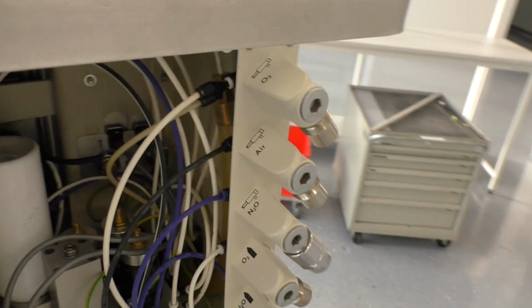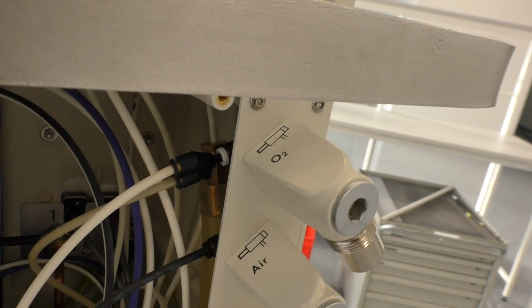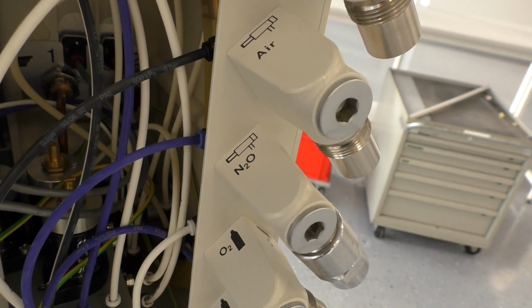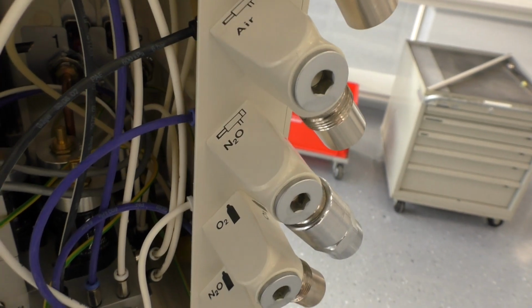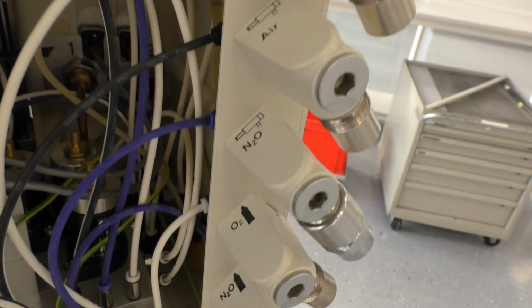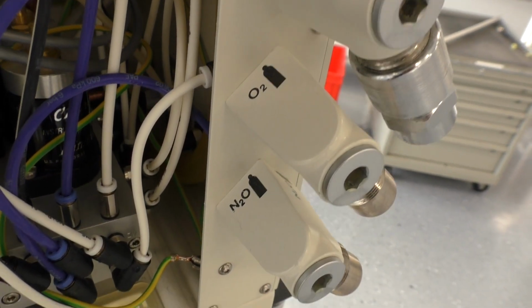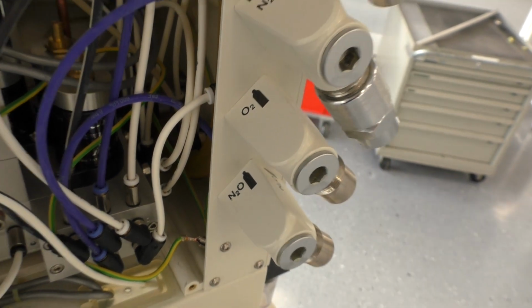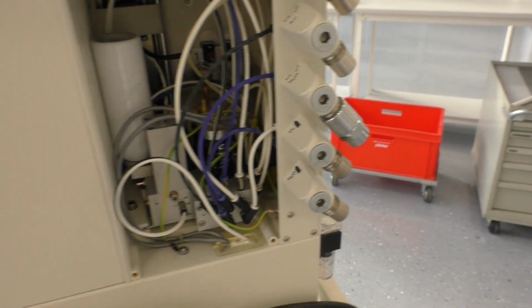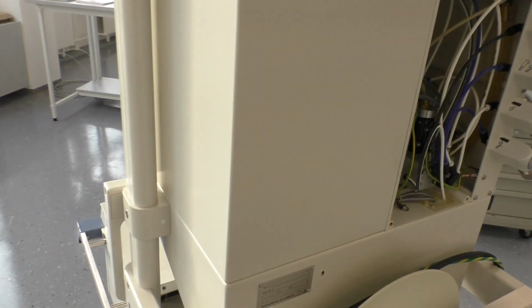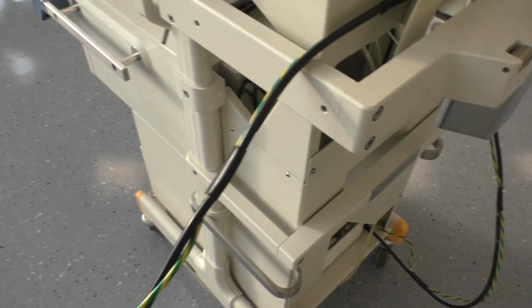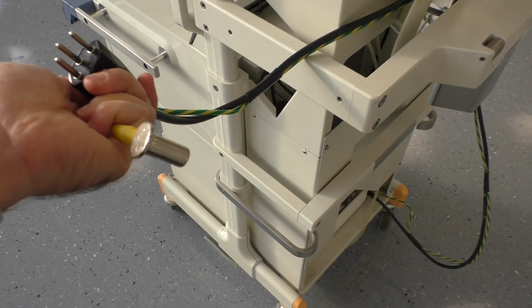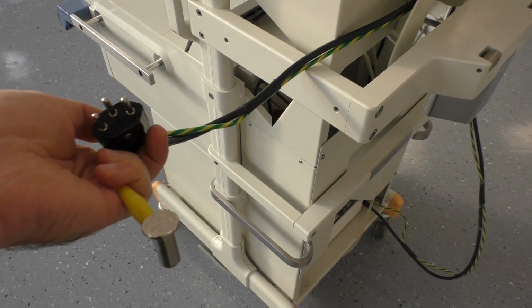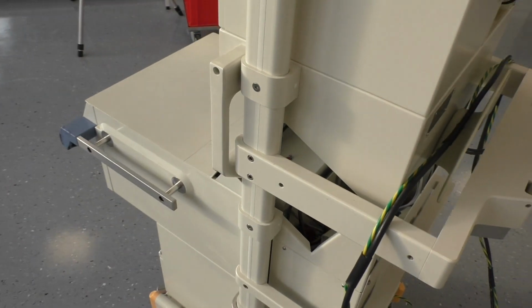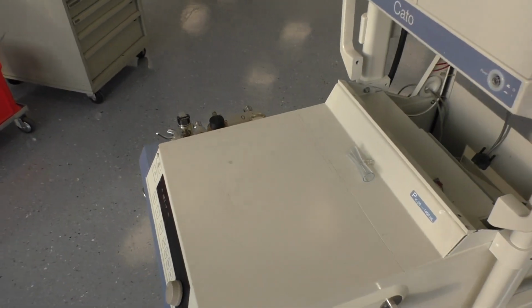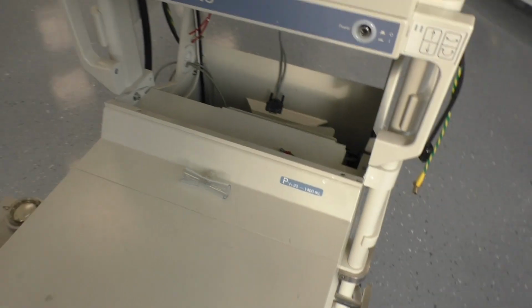Here we have the inlets for oxygen, air and nitrous oxide from the hospital pipeline supply. Then we have oxygen and nitrous oxide from bottles, so that's the backup in an emergency situation. Then typical for medical equipment is this additional earth plug. That's very important, so that the patient doesn't get hurt by an electric shock.